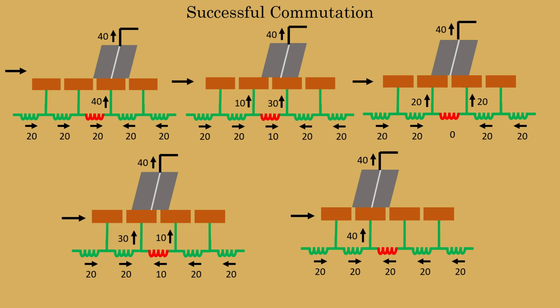As soon as the brush contacts the segment, some current will start to flow from the segment to the brush. How much of the total current flows depends on how much area the brush is contacting. As the contact area between the brush and the commutator segment increases, the resistance to current flow decreases. Current flow from the segment through the brush increases as the brush contacts more segment.